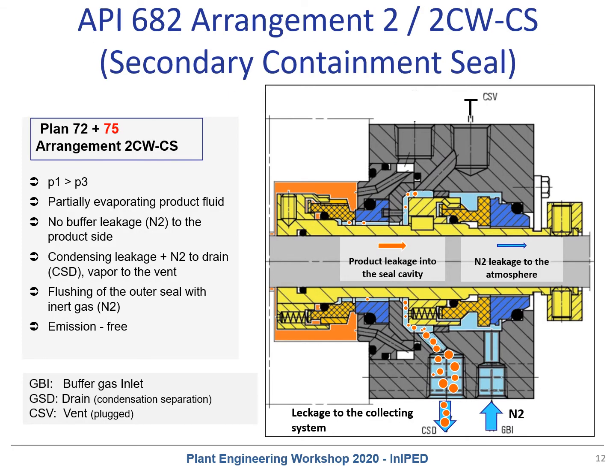Another seal configuration is also a dual unpressurized seal. The inner seal is the same as in the previous example, but the outer seal is now a dry running containment seal. The cavity between these two seals is filled with process vapor, which is the leakage of the inner seal. Containment seals are non-contacting gas seals running on process vapor, or with a piping plan 72 inert buffer gas purge. Process leakage which does not fully vaporize is collected in the piping plan 75.